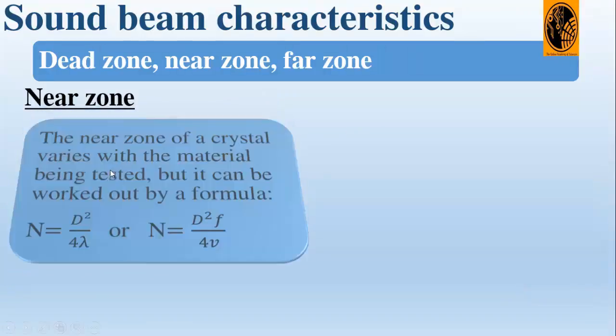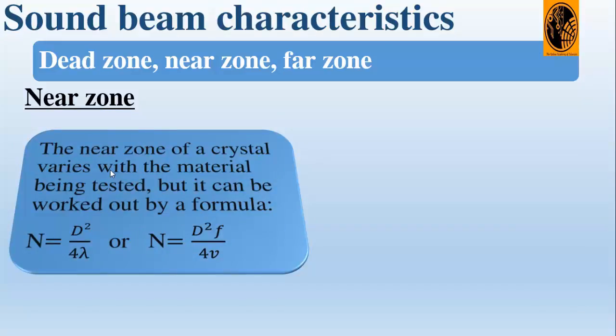The second zone is the near zone. The near zone of a crystal varies with the material being tested, but it can be worked out using this formula: N = D²/(4λ). Lambda can also be replaced by velocity divided by frequency.